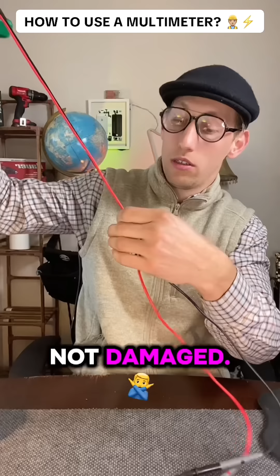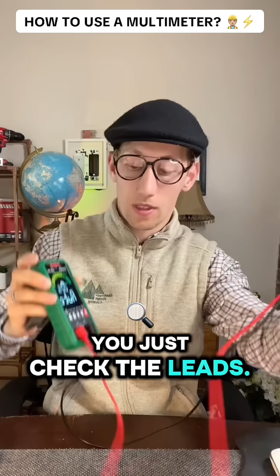Then, second of all, we have to understand if the leads are not damaged. That's the right way. You just check the leads. Third step is you go into continuity and test the leads. You need to hear a beep. That means the tester is working, the leads are not damaged.